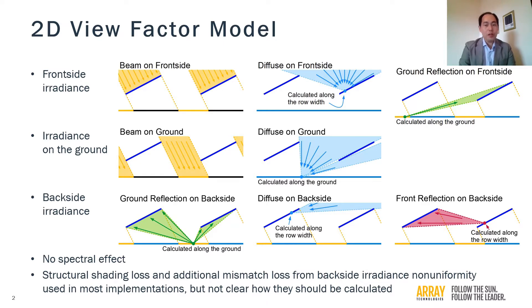The two-dimensional view allows you to calculate the front-side irradiance, irradiance on the ground, and finally the back-side irradiance, with computations simple enough to be carried out on a desktop computer. Some limitations of this model are that the spectral effects are ignored, and that there are no clear guidelines as to how to estimate the structural shading and backside irradiance non-uniformity loss factors, which are used in most implementations of the model.